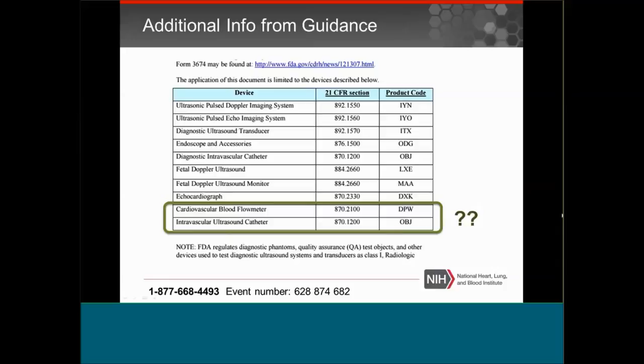Well, one thing you can do is, I showed you how the 510K database has a product code field. So you can search for something that has this product code, and in the prior slide, those codes were DPW and OBJ. And so I went ahead and pulled up one 510K summary from each of those product codes. And if you note over here for the Transonic Systems technology, it is a simple single product code, DPW. And I can take a look at its intended use and determine whether or not this might be an appropriate technology for me to reference for my substantial equivalence.